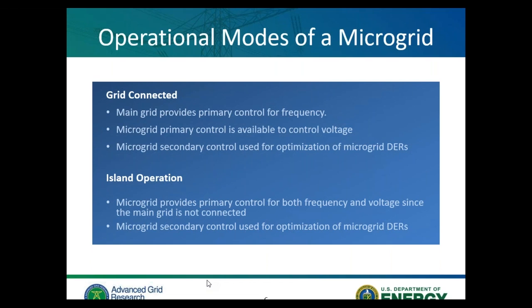In the island operation mode, the microgrid now provides primary control for both frequency and voltage, since the main grid is not connected, and the secondary control is used for optimization of the microgrid DER.